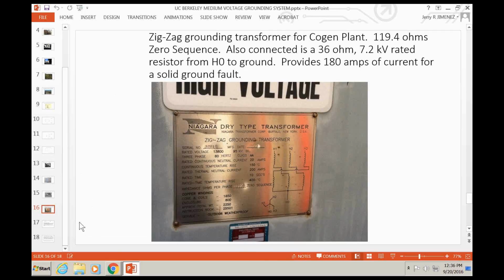Phase-to-phase, because of the low resistance grounding, if we get a phase-to-phase fault or a phase-to-phase-to-phase fault, a three-phase fault, the ground resistors are pretty much not a factor. We get real high currents because we have nothing to limit that other than the transformer impedance and a little bit of cable impedance that we have.